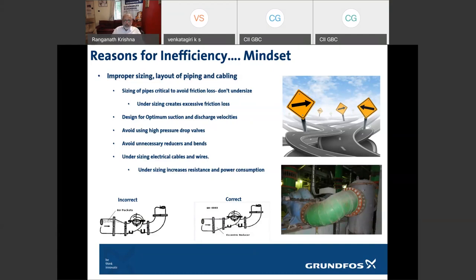Then valves: where you can avoid a valve, please avoid a valve. Or if you have to have a valve, please ensure that the valves are sized right and there are no high pressure drops. Avoid unnecessary reducers and bends. These are simple, common sense engineering practices, which are no longer common. We have got into an era of looking at a screen and asking software to tell us what to do. We have lost that little bit of sense which says, this is good engineering practice, this is what it should be, because everything comes out of basic physics, chemistry, and biology. And if we tend to forget that, sometimes we lose the good things, thinking that all the answers will be given on the screen. They are not, unfortunately.